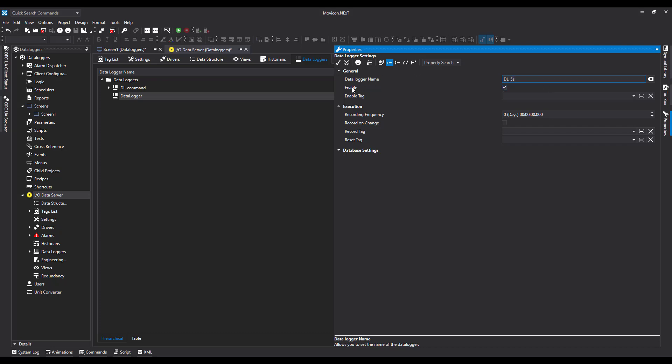We have Enable and Enable Tag - we're going to come to Enable Tag in a few minutes. In Execution we have Recording Frequency: days, hours, minutes, seconds, and milliseconds. I'm going to set mine to 05, so every 5 seconds it's going to take a snapshot of the tags that we assign to it.